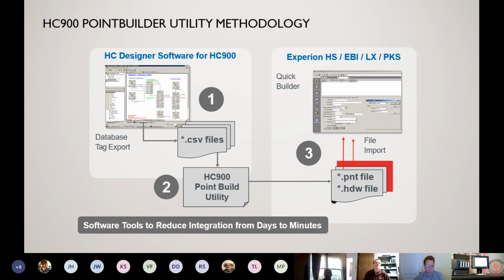One of the next features of the software allows you, after you are done programming your configuration for your application, to export the tag database and build a point database that can later be imported into a Honeywell SCADA system like PKS, Experion HS, Experion LX. It's also used for a lot of our building control systems where they're using similar SCADAs. Maybe the HC900 is used on multiple air handling units communicating to an Experion EBI system, where this allows you to very quickly, without duplicating the points in your SCADA, import the CSV file, and your point database is built for you within seconds.